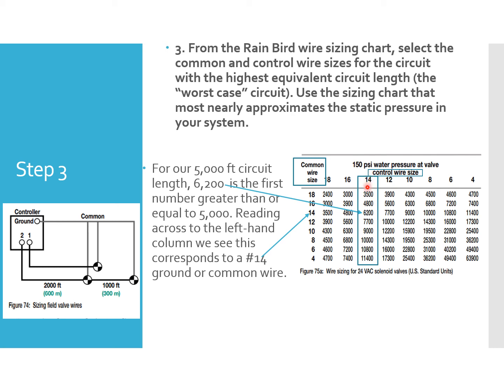And we come down here and we have 4,800, not quite right, and then we have 6,200. So it looks like both of the wires going to the valve, the common and the control wire, both need to be 14 gauge. Sometimes your common might be a little bit bigger size, and then your control wire can be a smaller size. In this particular situation, both wires will be the same size.